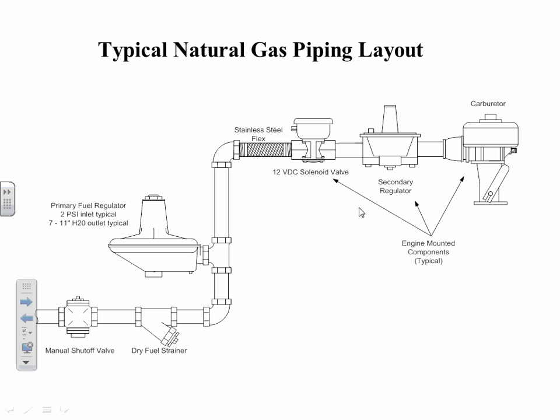But the solenoid valve, once the transfer switch sees that there's an outage, and we'll get into this again when we cover that, one of the first things that happens is that the engine will get a start signal, and it'll open this solenoid valve at the same time. So it's letting that 7 to 11 inches of fuel pressure in. And then a secondary regulator mounted on the engine knocks it down a little further in the ounces range, and then it goes into the engine.